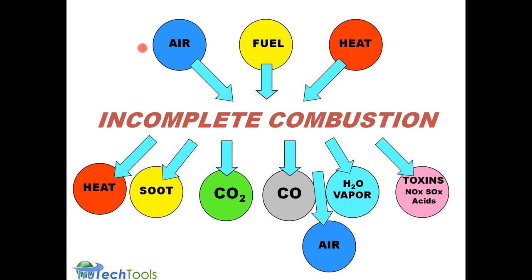You also have excess air coming into the system that actually moves out through the combustion system. So this is more the real world. It's a little bit more complex than the perfect world, of course, and we'll show you how the combustion analyzer addresses every one of these parameters. Because you can't really conveniently measure air, fuel, and heat. You can measure heat, but not the heat flow. The combustion analyzer looks at what happens on the other side of combustion.